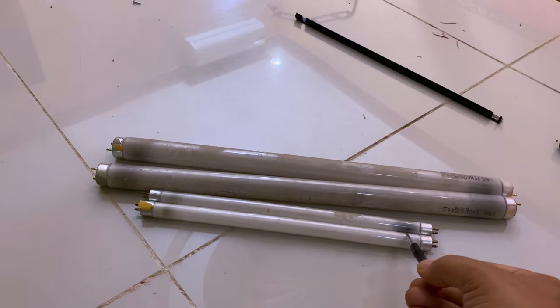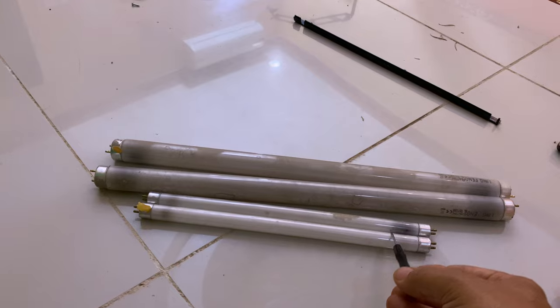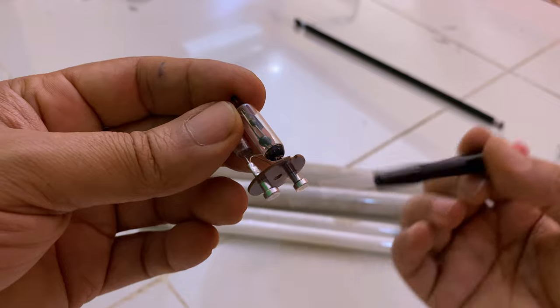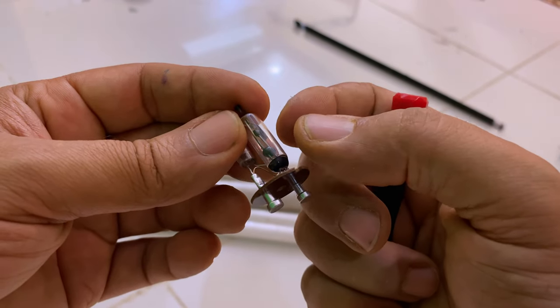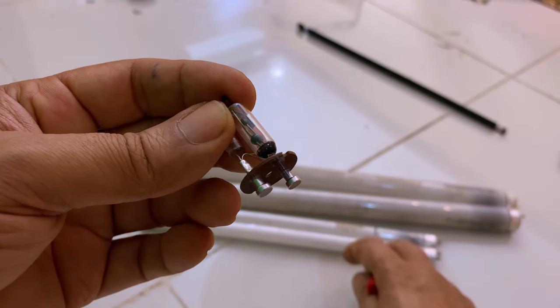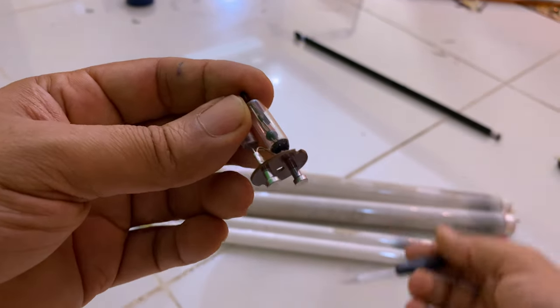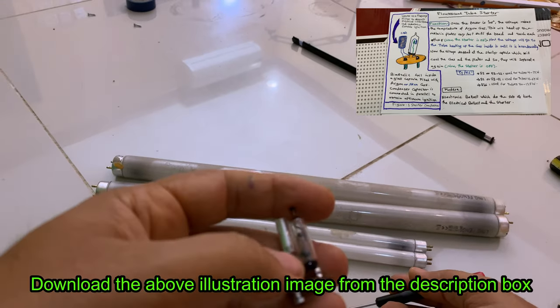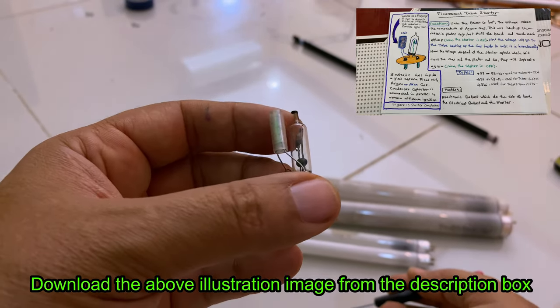If there is a problem like this, you can see the burn here, it fails to illuminate. So this one will repeat the process again and connect again. And this one will try to illuminate, but it will fail. And this will continue, damaging this one and also damaging the starter. I think I will make some drawings and I will try to upload them. I'll give you the link in the description box, guys, for those who like to understand how the starter works.